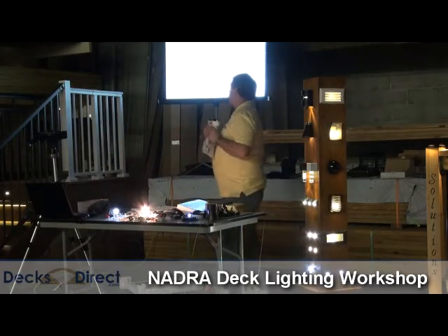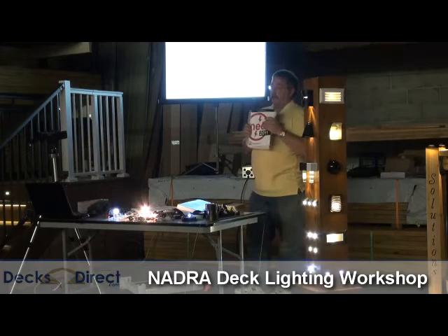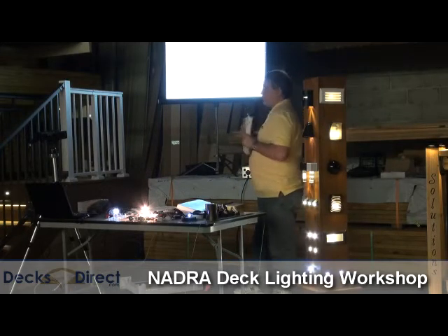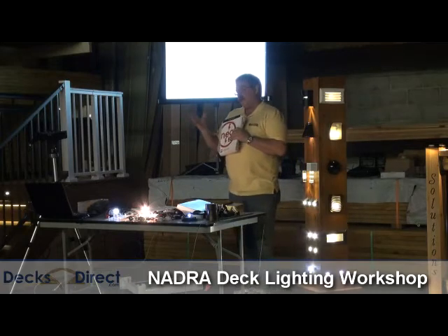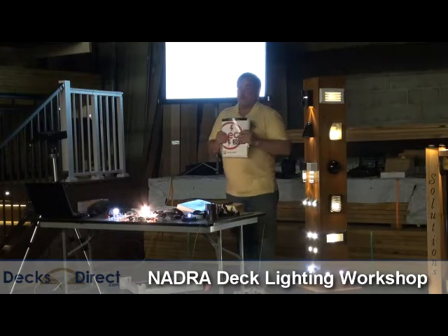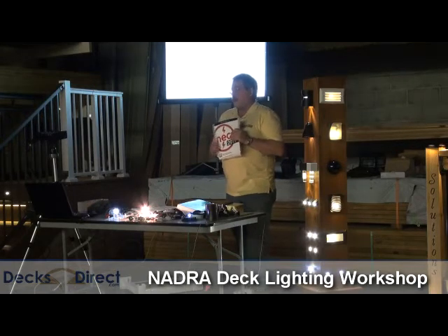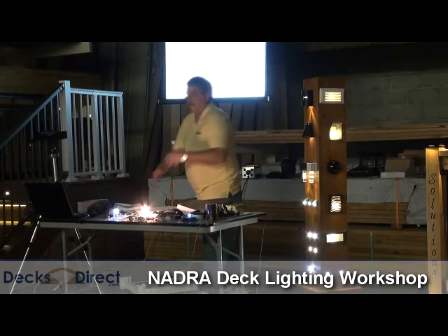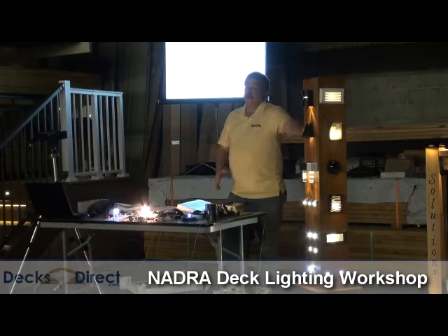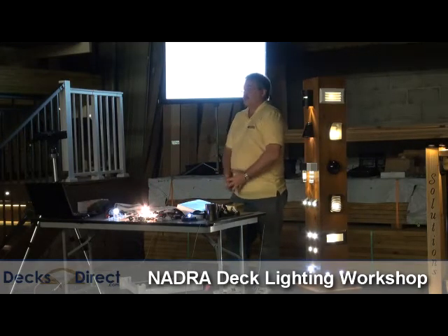This is a big one. This one has to do with safety. It's the hot tub rule. It's the NEC Rule 680. When we build a deck, somebody's going to put a hot tub on there. Lots and lots of stuff can happen. There's a lot of voltage included. It has little to do with lighting, but it can affect us. None of these lights are allowed by code to be within 5 feet, 60 inches of a hot tub.